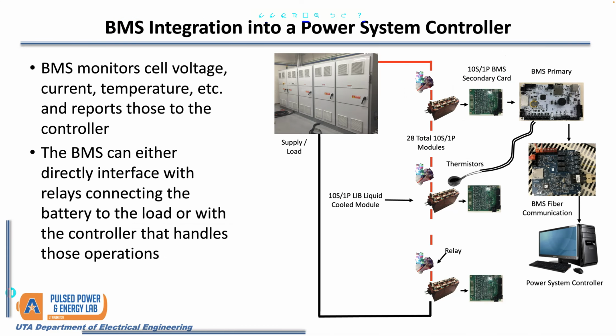So how would we begin to integrate a BMS into a power system controller? To begin, like I showed on the last slide with that LabVIEW plugin monitoring voltages, each module, just like the BMS shown earlier, interfaces with a secondary card. Each secondary card can monitor 10 cells. You get enough secondary cards to reach the top of your battery, and all of those connect to a primary where the data is collected and can be interfaced with a power system controller. The output of your battery would be hooked up to a supply or load that the power system controller communicates with to charge or load the battery.